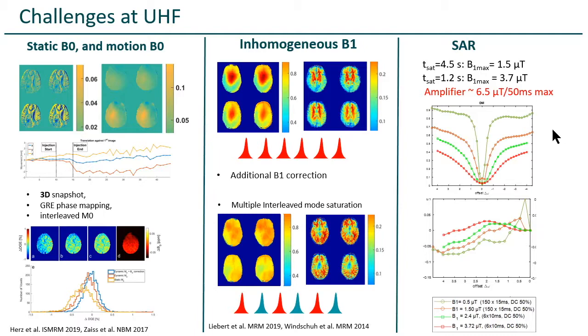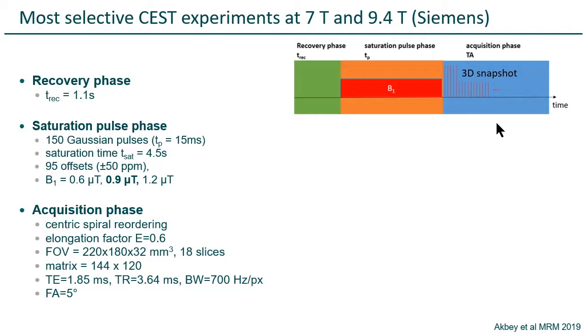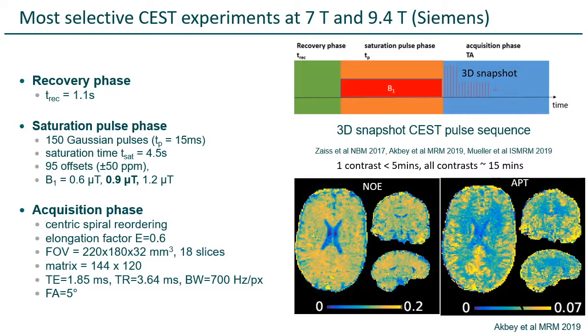If we solve all these problems, we can have the most selective CEST experiments at 7T and 9.4T — well, also at 3T, but the higher the B0, the more selective you can be. I use relatively low saturation power with a fast 3D readout, and we are now able to have whole brain coverage. This is work from Tony Stöcker's group, from Susanne Akbey. The readout for one image is below a second. We can have one contrast below five minutes, and all contrasts including B1 correction in approximately 15 minutes.